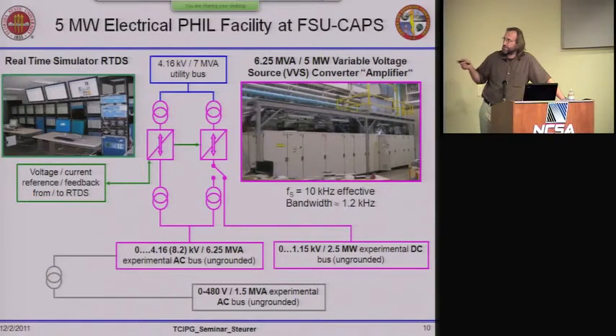this converter system is comprised of two sets of converters. They are completely independent, really. Two independent converter strings that both pull power from our utility feed, but can be controlled independently on the output. So I either use them in tandem when the switch is in this position, in tandem to provide 6.25 megawatt at this bus where I control the waveform, or I switch this over to the DC side, leave this transformer alone. I have half the capacity on this bus, still AC, and I have half the capacity more or less on the DC side.